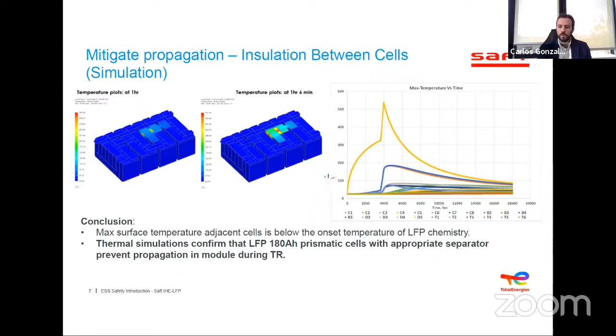So the target here is, if we have a thermal runaway or an issue in a cell, to reduce or avoid this cell propagating and activating the cell nearby, causing this thermal runaway reaction in all the cells and modules. So this is one of the first steps to avoid fire issues at site.